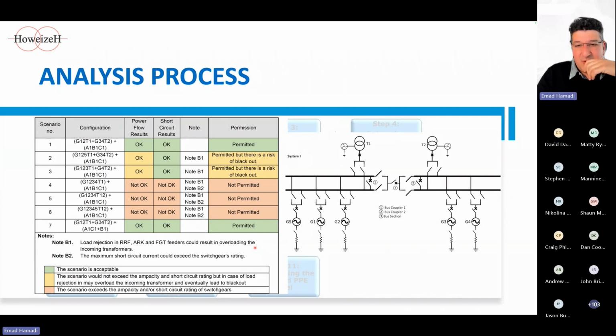Okay, one more thing while we are on this slide. I come across many sites in the UK, especially waste-to-energy power plants, where they normally connect the steam turbine directly to the main bus bar, like an 11 kV bus bar. This is okay in general from a design perspective, but it will result in high asymmetric fault currents, which have a high decaying DC component. That causes the risk of the circuit breaker opening in non-zero current and potentially damaging the circuit breaker, especially if it's not capable of handling that amount of DC component.